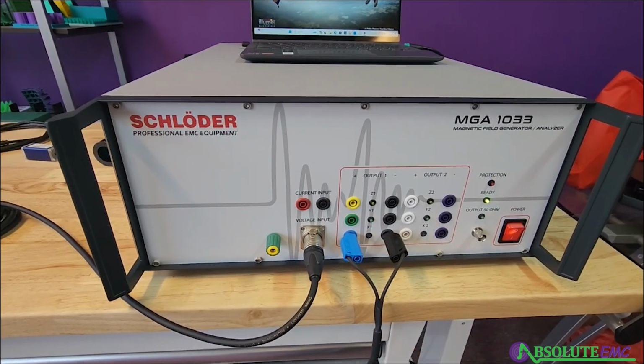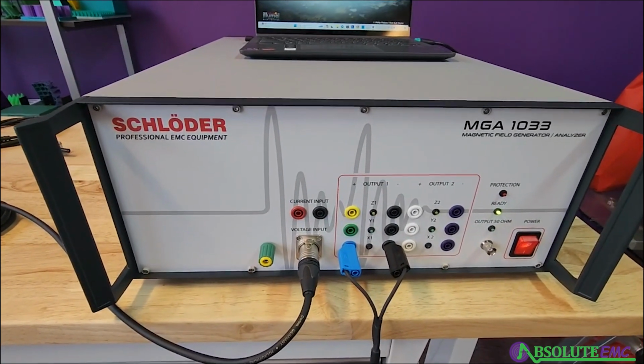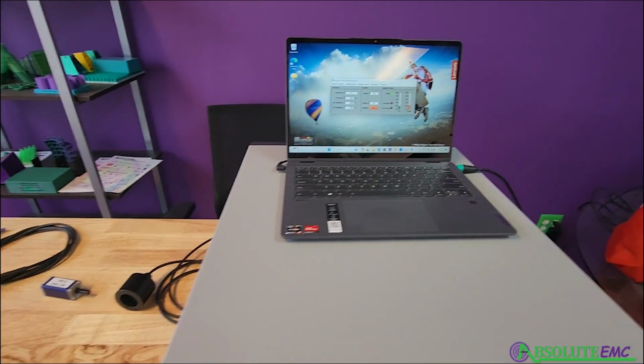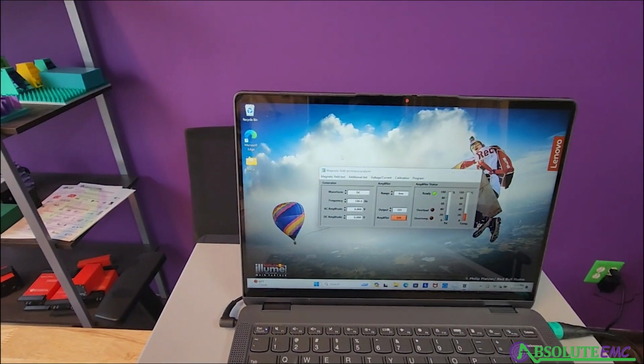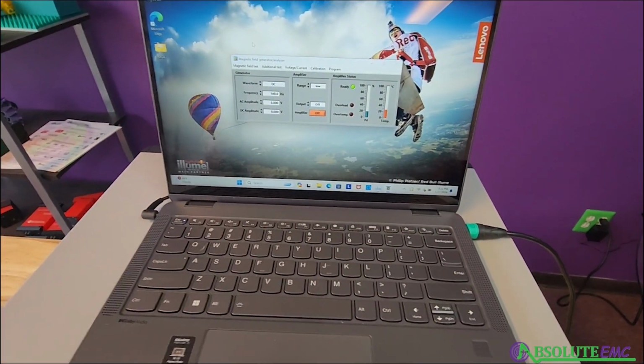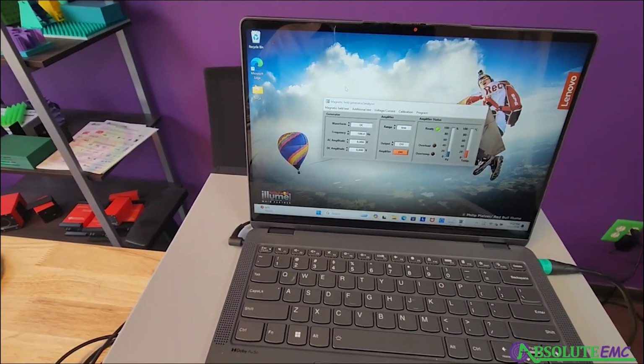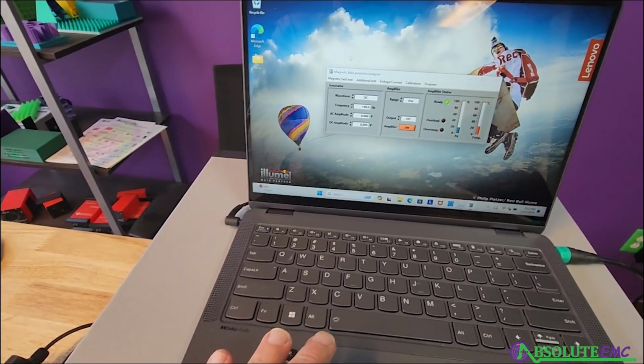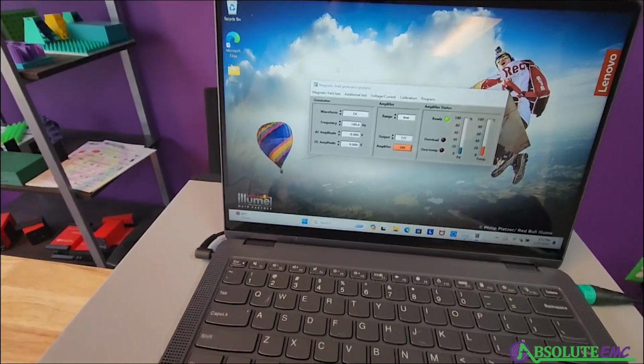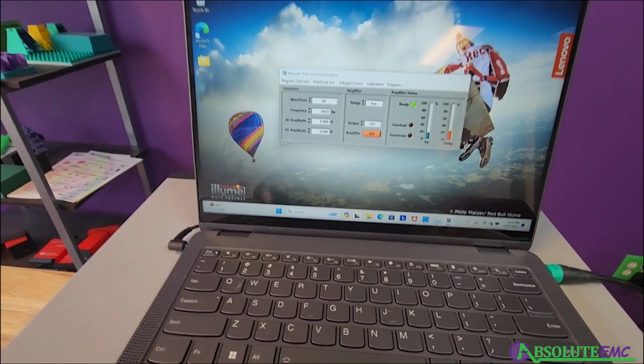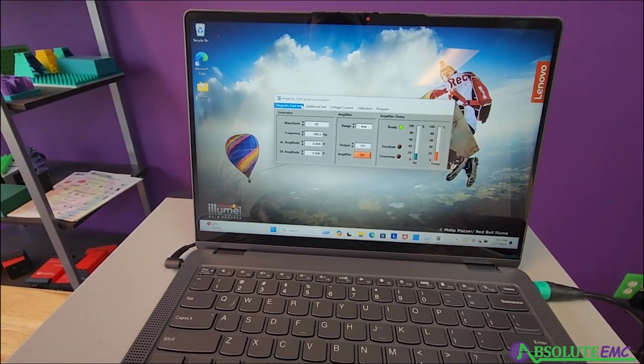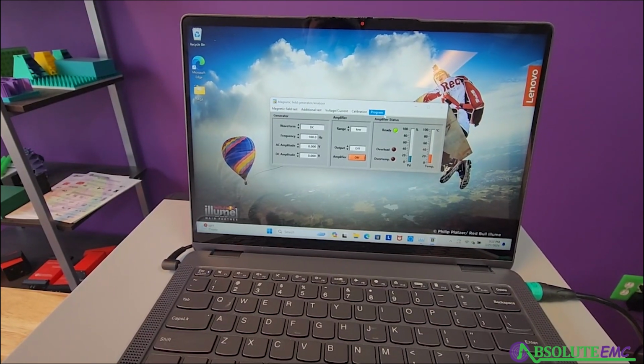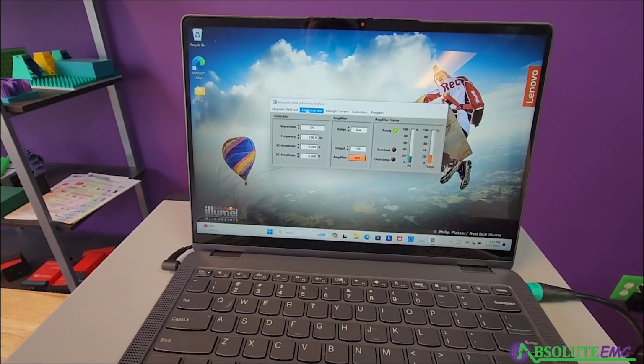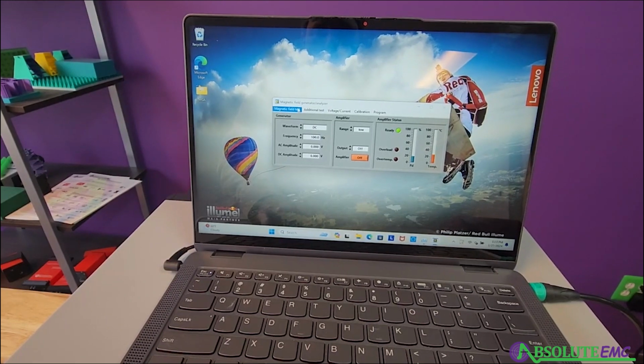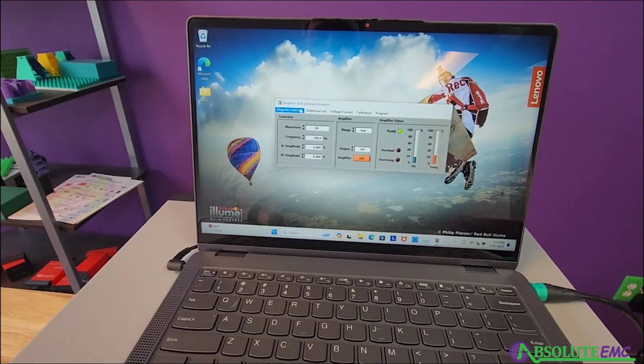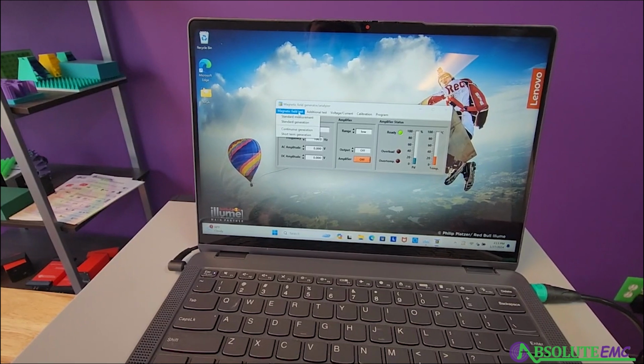Some minor clicking happens inside the generator. You know it's connected and working. So the system is connected through the USB connection. And that's our opening screen. So up here you have a couple different selections of where you need to go. So we're set up to do a radiated magnetic immunity test. So we call them the magnetic field tests.